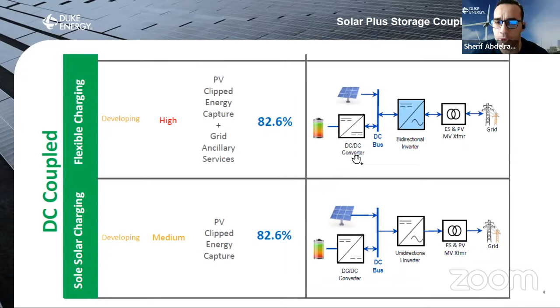Now on the efficiency side, contrary to common belief, both are actually somewhat less efficient compared to AC coupled systems, especially low voltage AC coupled systems. That's mainly because DC-DC converters, for the most part, have a bit less efficiency than inverters, so it's more taxing to go through a DC-DC converter twice versus going through an inverter.